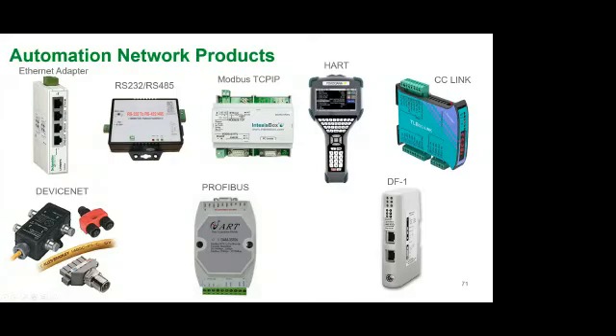HART is one more form of communication. CC-Link, DeviceNet, Profibus, and DF-1 are different types of communication schemas which are used to communicate with field devices. The field devices may be non-communicable to Ethernet, so we need all these types of devices to convert the signal and collect them to the controller in an understandable format.